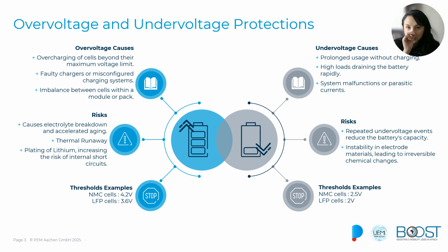And let's begin with the two main voltage protections that are the over voltage and the under voltage. To start then, let's begin with the over voltage. Basically this protection occurs when the voltage of any of the battery cells exceeds its maximum safe limits. This can happen because of several reasons. For instance, if we overcharge our battery, if we use faulty chargers, and if we have batteries that are imbalanced, all of those can cause this protection to be triggered.